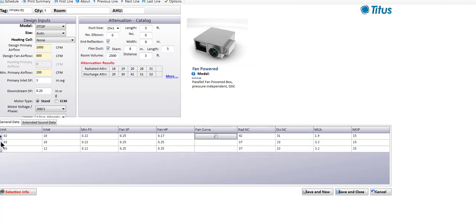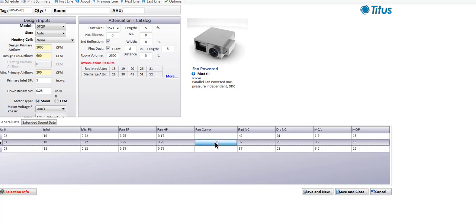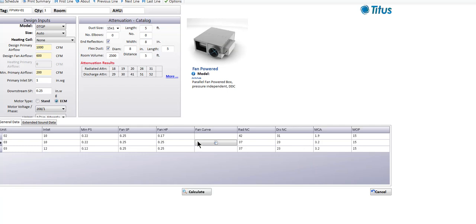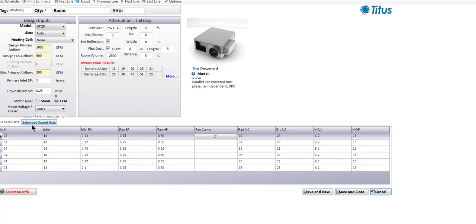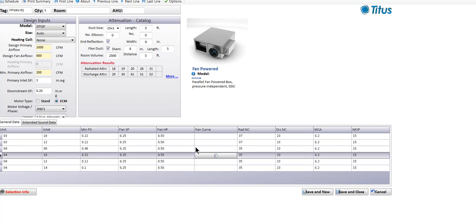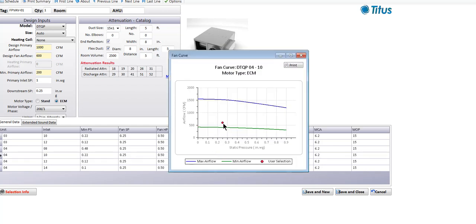Looking at the size 3 unit, it's kind of low in the efficiency range for a PSC fan motor, but you have plenty of room for adjustability. Both of these are kind of problematical. Let's take a look with an ECM. Now we've got more choices — looking at a size 4 with a 10 inch inlet, that's a very, very efficient operating point. I kind of like this operating point better than anything else I've seen. I'd probably go with a DTQP size 4 with a 10 inch inlet.